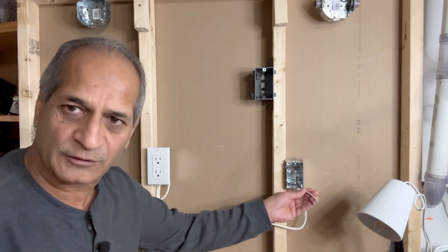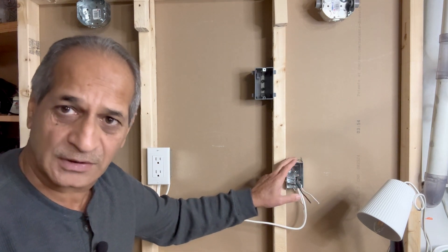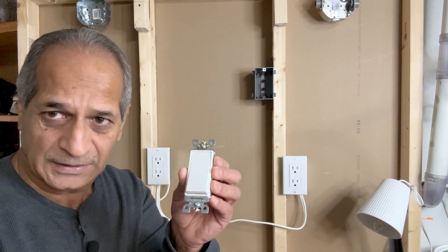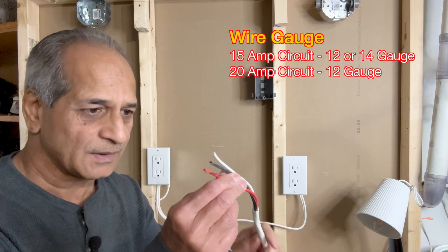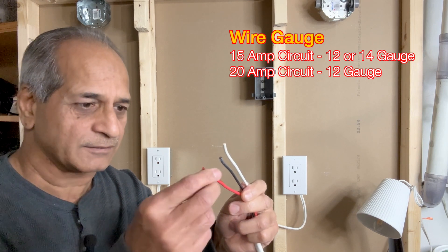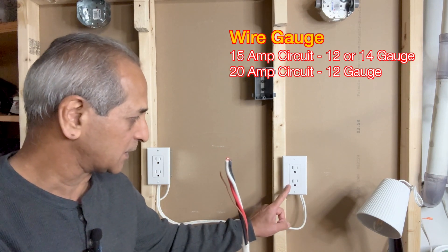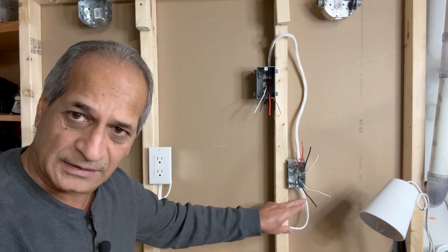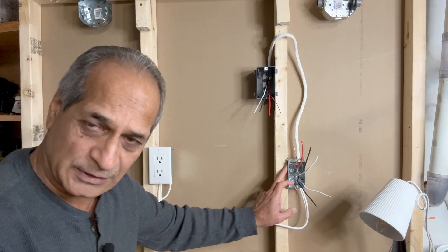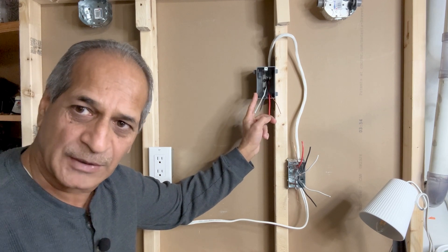This is my outlet box which has a 14-2 wire that brings power into the box. From here, I will take a 14-3 wire from this box to the switch box and then connect the wires. I will need a switch for this project and I am using a Leviton Decora single pole light switch. I will also need a 14-3 wire with white, black, and red wires in it, along with a bare copper ground wire. This 14-3 wire will go from the receptacle to the switch box and I will use Wago lever nut connectors instead of wire nuts. Once again, this 14-2 wire brings power into the outlet box and this 14-3 wire goes to the switch box. I will now strip these wires and make them ready for connections.